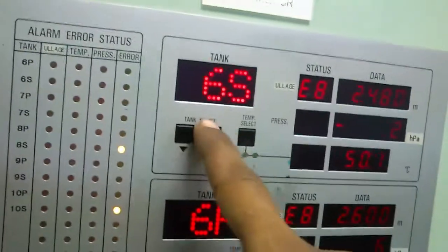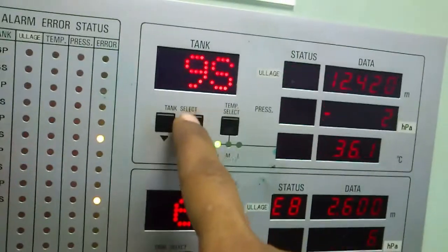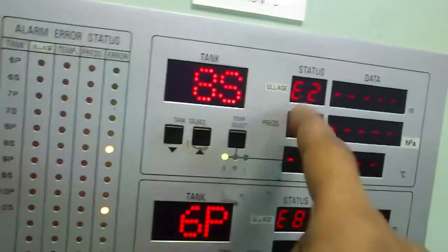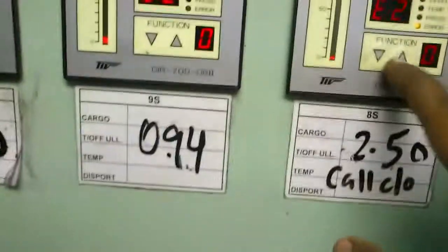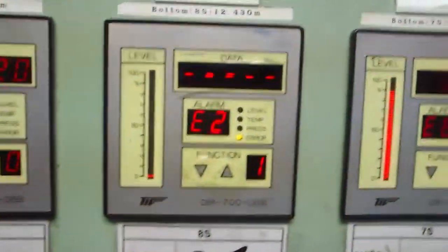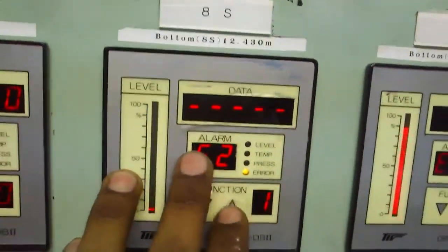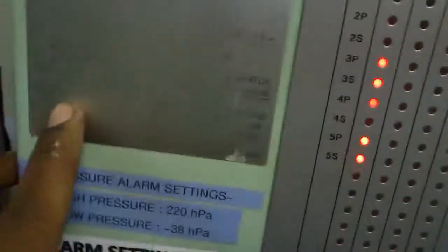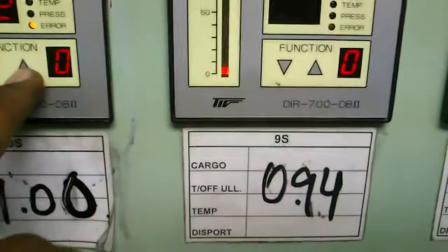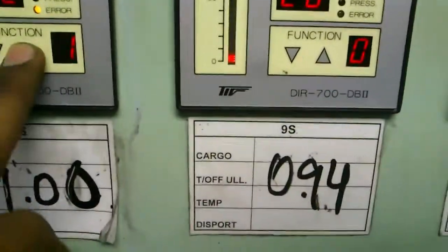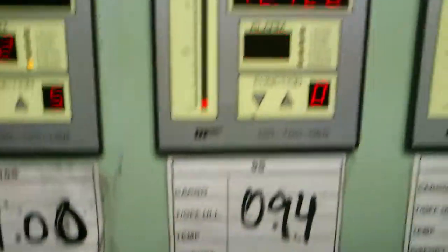That's six port, six starboard, seven port, seven starboard, eight port, eight starboard. This E2 eight starboard is E2 is coming. This has some problem with the gauge that's why E2 is marked error. Same as 10 starboard also has got some problem with the level gauge. This way normally E2 error comes.